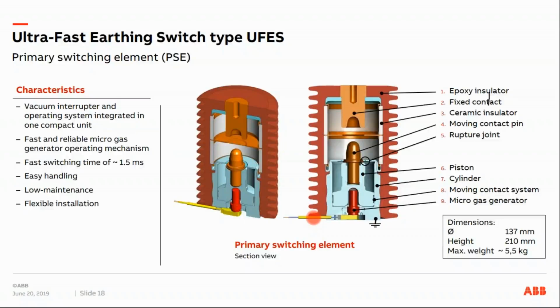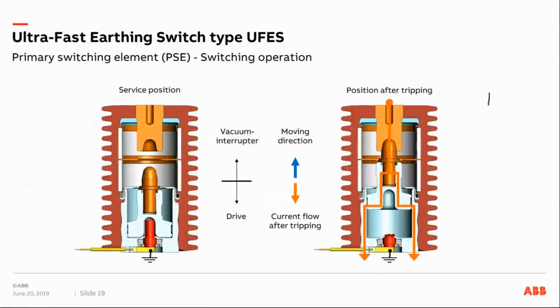After detection of the arc fault, at almost the same time, the gas generator is activated, and more specifically, let's move to the next slide, and you can see it in a better way. The gas pressure drives the movable piston, which is at earth potential in its initial position, into the fixed contact socket, which is at busbar potential, and that creates a solid metal short circuit to earth. So here you can see how the current flows after tripping. And after the operation of the primary switching elements, since this is a one-shot device, the primary switching elements need to be exchanged.